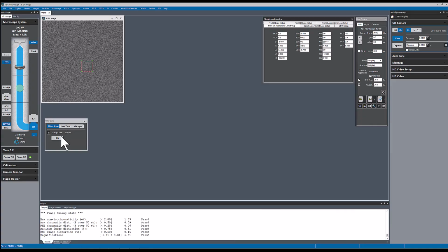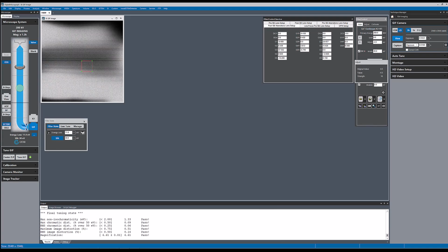So if I insert the slit, the way that we do this is we have the slit inserted, and then we sweep the slit over the field of view of the detector, and we end up with an isochromat, or an isochromatic surface image, at the edge. The symmetry in this isochromat gives you an indication of how well tuned the isochromaticity is. And that's pretty much everything.